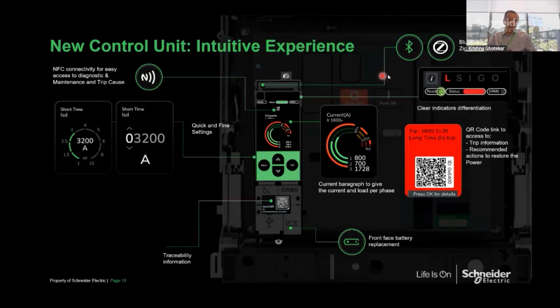On top of the trip unit, in terms of LEDs, we have made it in a much more user-friendly way. So there is a ready LED which continuously blinks. This comes from the legacy of compact NSX MCCBs back in 2008 till now. So what does the ready LED indicate? Whenever it glows, it means that the microprocessor is working properly, the CTs are connected. With every blink of this ready LED, it checks the complete continuity of the microprocessor, the CTs, the toroid and all the accessories. And then there is a status LED which is added new. Again, depending on pre-alarm or post-tripping, it will change the color.